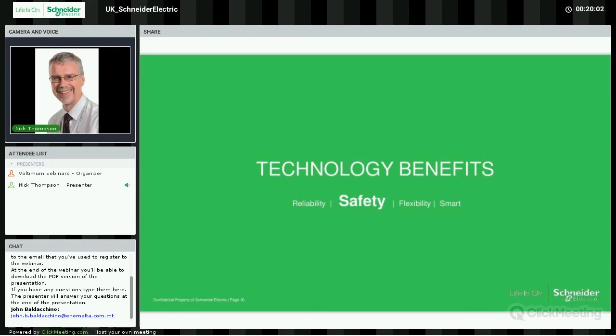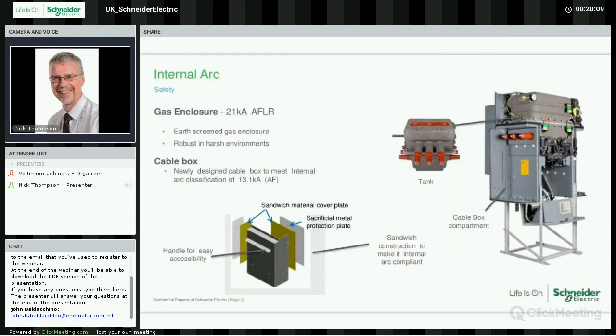Safety is, as I've already said, foremost of anybody's mind, and the IEC standards which we work to are very exacting on not only how we test them, but also how we achieve a pass when we subject the units to a test. Now, an internal arc is a very rare occasion, but if it does happen, then it's catastrophic not only for the equipment, but could also be catastrophic for anybody who happens to be in the vicinity of a switchgear which has been subject to that fault.